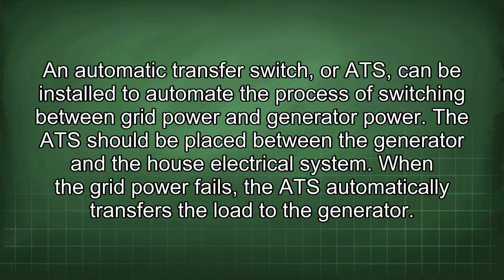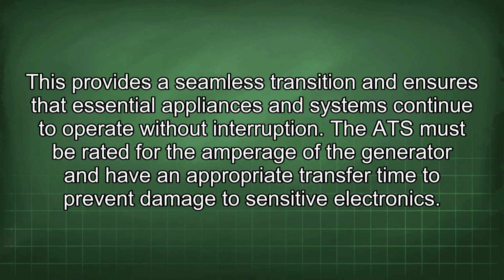An automatic transfer switch, or ATS, can be installed to automate the process of switching between grid power and generator power. The ATS should be placed between the generator and the house electrical system. When the grid power fails, the ATS automatically transfers the load to the generator. This provides a seamless transition and ensures that essential appliances and systems continue to operate without interruption.